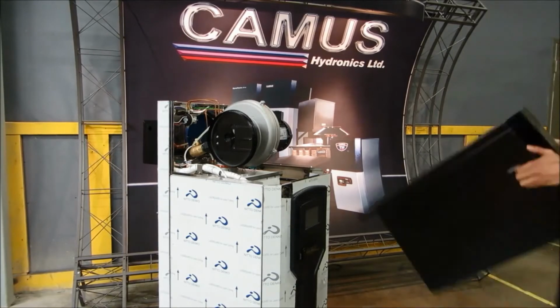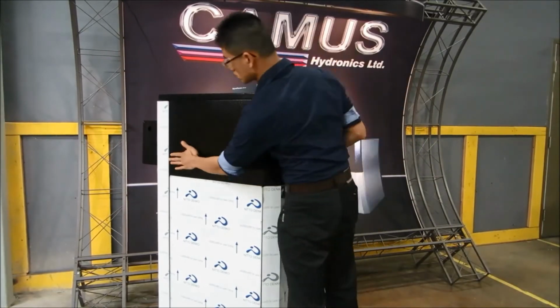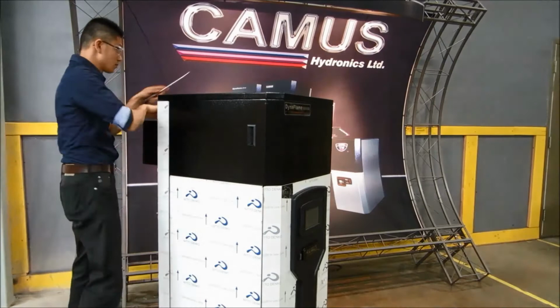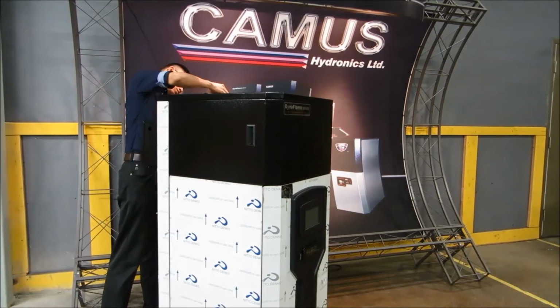Verify that ignition is smooth and rumble-free. Using your combustion analyzer, you will need to verify that the combustion readings coincide with what is stated in the I&O manual.